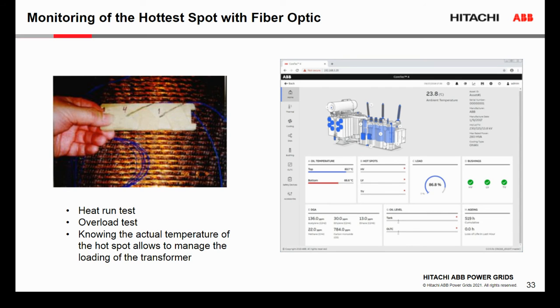Many times the hotspot in the windings is monitored by current transformers, but this solution does not use direct measurement. It is called thermal image. To measure directly the temperature of the hotspot inside the winding, we have to install fiber optic probes inside the spacers between the first few disks, and this gives us the actual temperature of the hotspot.